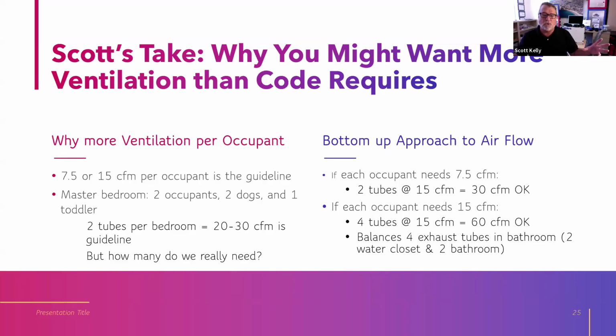And now when you look at this whole equation, you put it all together, it actually makes total sense. You've got the 4 in the master bedroom, you've got the 4 in the master bathrooms, and you're changing the air at an equal balanced rate. And you can actually measure the supply air and you can measure the exhaust air and have a true balance in them by doing some little adjustments with some of the dampers on the inside. So that's kind of the approach of how do you size this thing? How many people are in there? What does code say we have to do?